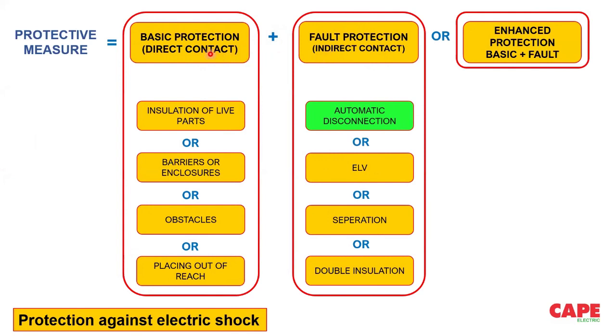Basic protective measures include insulation of live parts, barriers or enclosures, obstacles, and placing out of reach. Say, for example, barriers or enclosure. A live bus bar is inside a panel board. It is inside an enclosure. It is a classic example of basic protection. But once you put a live part inside an enclosure, there are several safety measures which you are supposed to carry out in the enclosure. Don't think that by putting a live part inside an enclosure, you are achieving safety. It is not like that. There are several rules which we are supposed to follow.